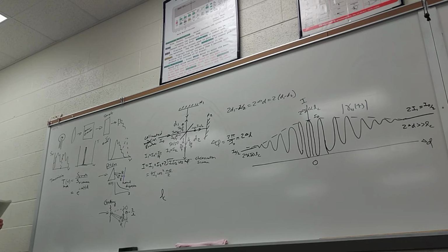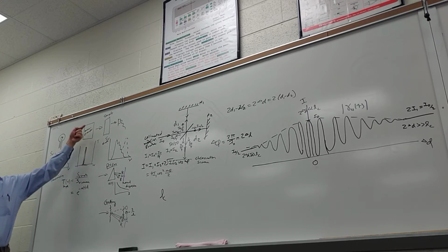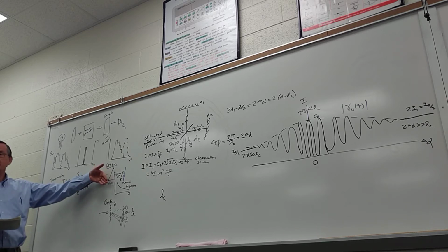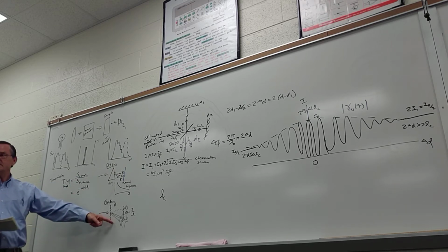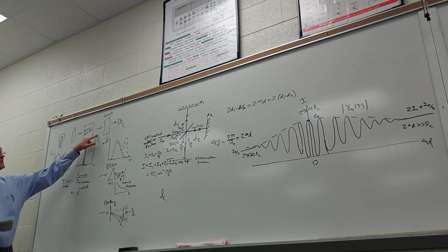Although you'd really like a monochromator where a beam comes in, and then that same beam comes out collinearly, with no angular deviation, no spatial deviation. You just want it to go collinear all the way through. So that's where the complicating factors happen. Because here you've got angular deviation as you move the slit, and spatial deviation as well, likewise over here. So it becomes a matter of how you construct something to get this kind of geometry, because that's what's most convenient in an instrument.